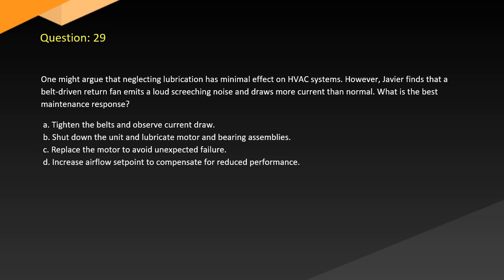Question 29. One might argue that neglecting lubrication has minimal effect on HVAC systems. However, Javier finds that a belt-driven return fan emits a loud screeching noise and draws more current than normal. What is the best maintenance response? A. Tighten the belt and observe current draw. B. Shut down the unit and lubricate motor and bearing assemblies. C. Replace the motor to avoid unexpected failure. D. Increase airflow set point to compensate for reduced performance.